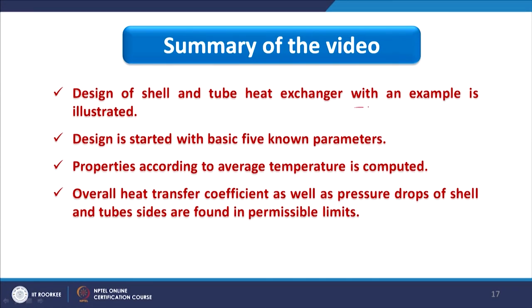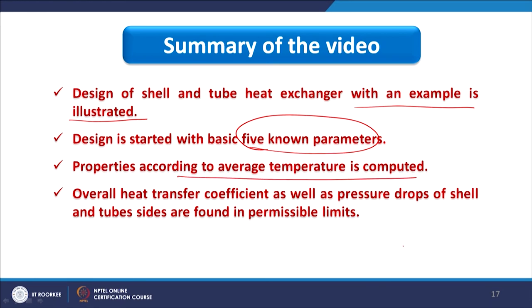Here is the summary of this video. We designed a shell and tube heat exchanger with Example 2, considering a toluene and water combination. Starting with five basic parameters, density data, and a pressure drop range less than 1 bar, properties were determined at average temperature as explained in Lecture 15. Overall heat transfer coefficient and pressure drops on both shell and tube sides were found within the permissible limit. Note: if pressure drop exceeds the limit on the shell side, you can reduce it by increasing baffle spacing and increasing baffle cut. Thank you.